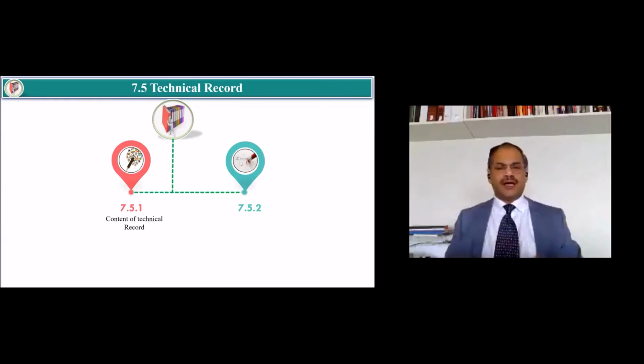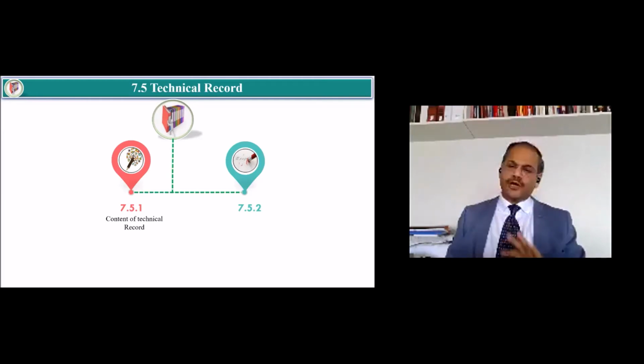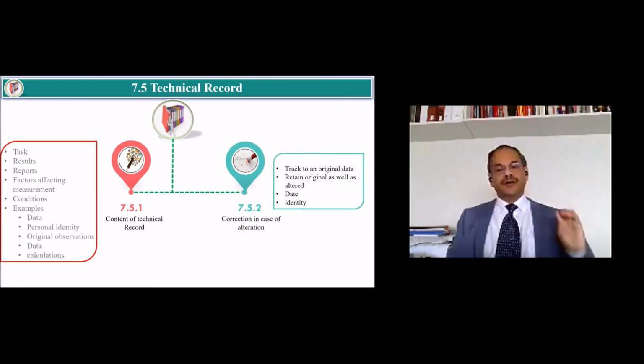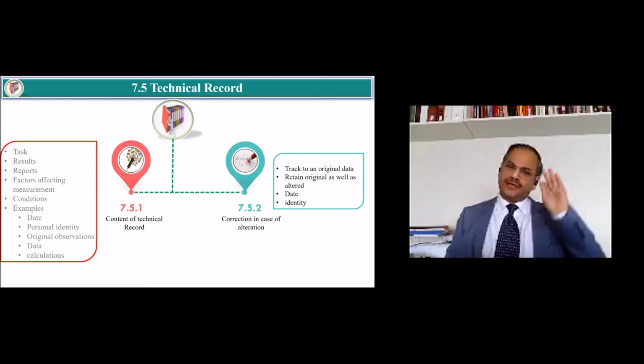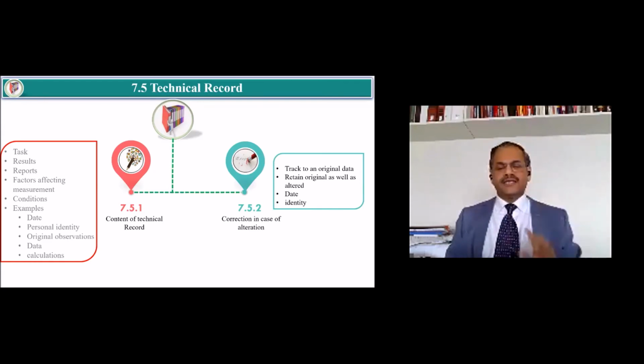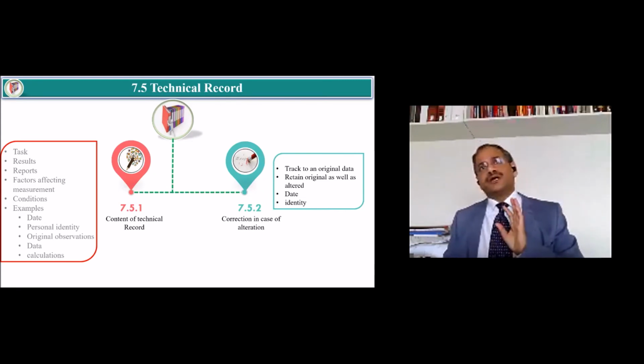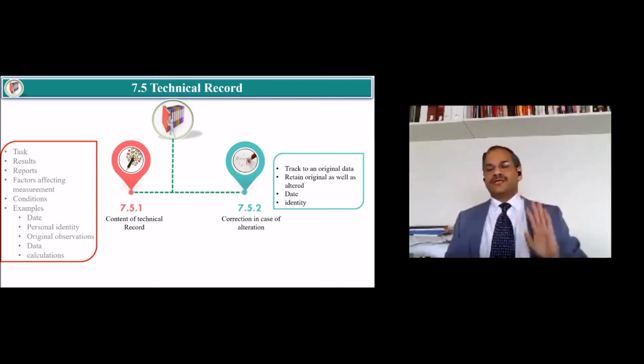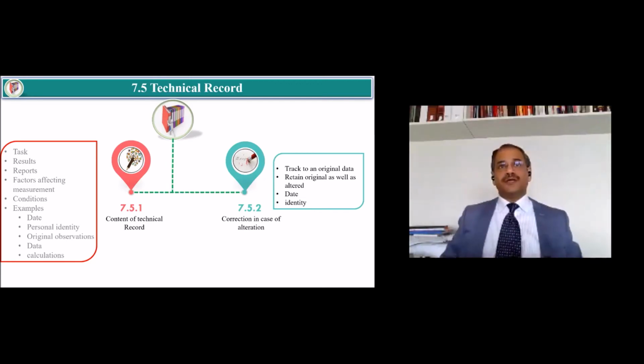Yes, there are different terminologies across the globe. Somebody says original observation, somebody says raw data, perfectly okay. But whatever you call it, it has to meet two requirements. Number one, what is the content of that technical record? That is 7.5.1, and it applies to each observation. If you are doing 100 tests, you have to have this data for all 100 tests. Then, what should you do in case of correction? Now, along with a LIMS, you may be transferring all your data directly from the instrument to the LIMS. Perfectly okay, that is your original observation. Your chromatogram shall be there in your LIMS.